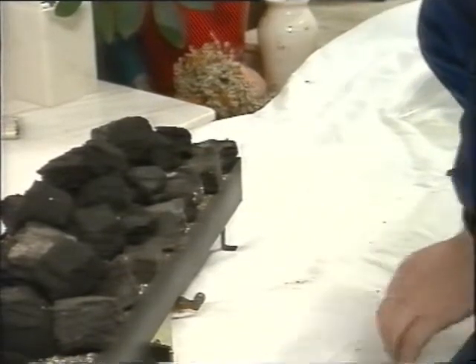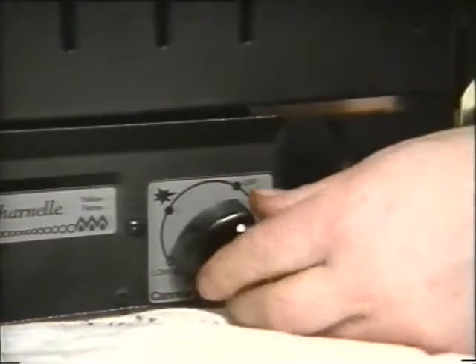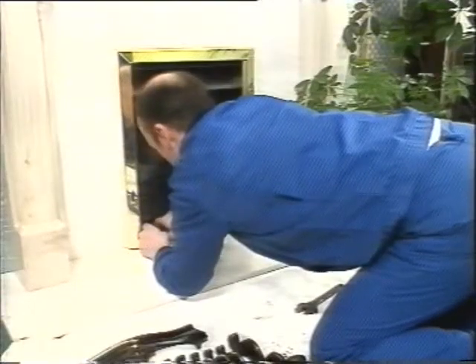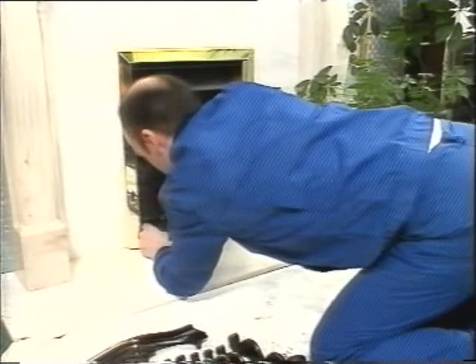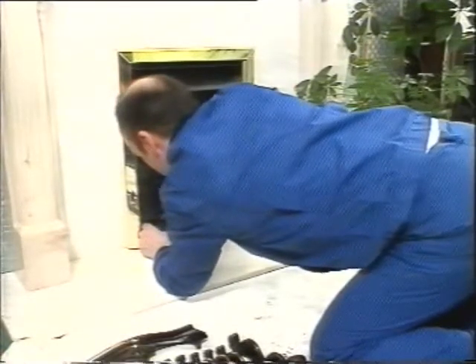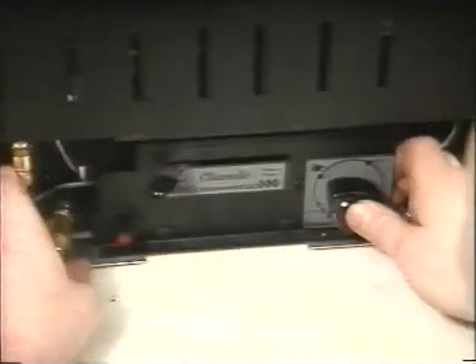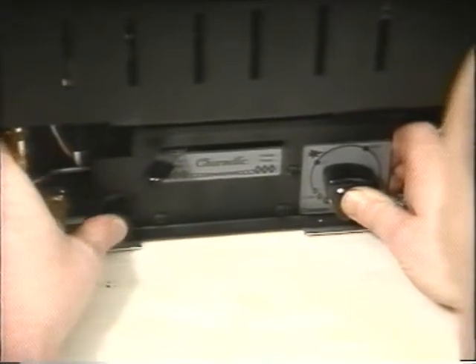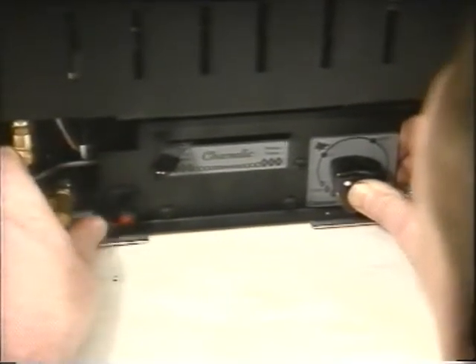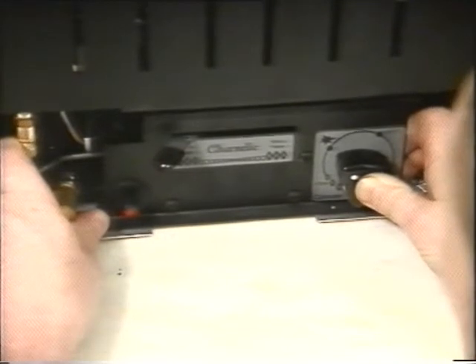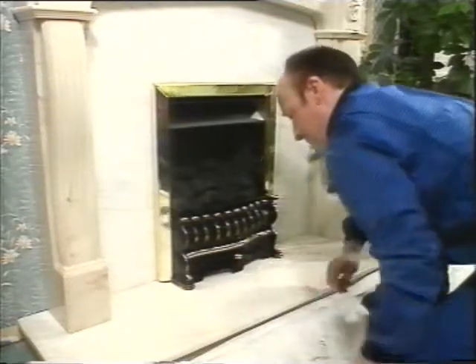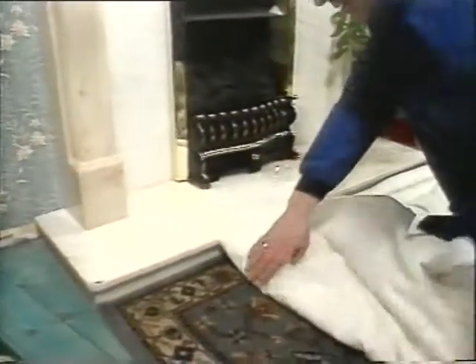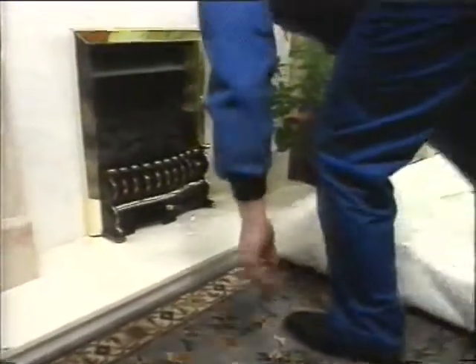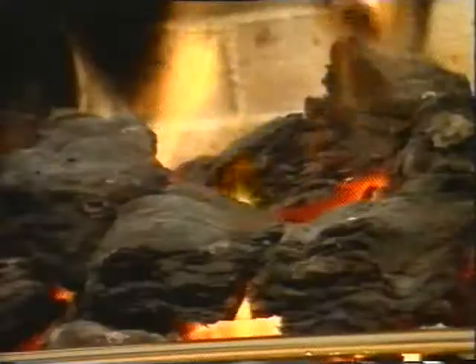Check the control tap and grease it if it needs it. And now you can put the fire back together, reconnect it to the supply and test again for soundness. If that's okay, check the ignition system and the flame safety device and see that the burner pressure is correct. When you've tested for soundness and the flue for spillage, you can clear up the work area and the job's done.